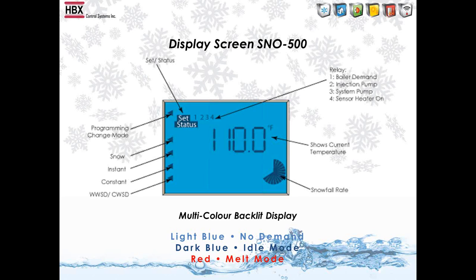We can see the user interface and which relays are on. We can see the current temperature, the snowfall rate, and whether warm weather or cold weather shutdown is on or off. The multicolor backlit display is one of the key features of the Snow 500. Depending on which mode of operation is selected, the screen will change to indicate the status of the system. Light blue means no demand, red is in melt mode, and dark blue is in idle mode.